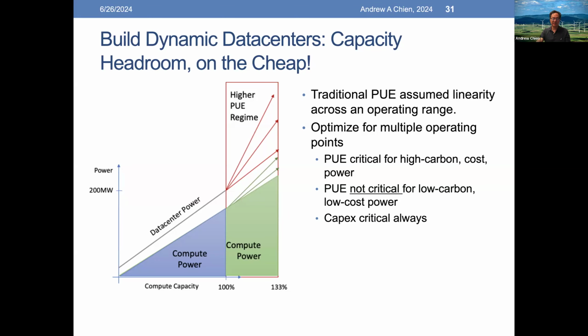The idea here is to optimize for multiple operating points. We have to keep the PUE. The PUE, of course, is critical for high carbon, high cost power. So when the cost of everything is really high, then we want the PUE to be as good as possible. But it turns out the PUE is not critical when we're dealing with an environment in which there's low carbon, low cost power, like I just showed you. There's excess renewable generation, there's lots of solar generation, and so on. So at those times, we're going to operate up in this range where we can have a higher PUE, and that's okay. And of course, the CapEx you have to pay for all the time.